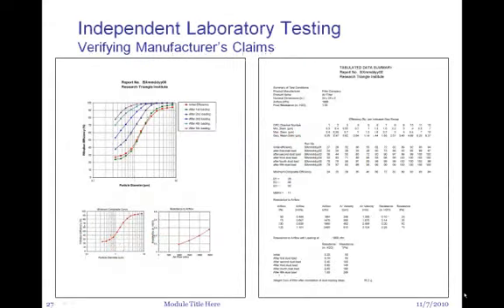One way to verify that the details are true is to request an independent lab test of the filters you're considering, to verify they really work the way the manufacturer says. You can go online and Google for independent laboratory testing of filters — you'll find organizations that do that, and most have sample reports. They test for pressure drop, particle filtration, MERV rating, and filter loading. They can pretty much verify that the manufacturer's claims are valid.